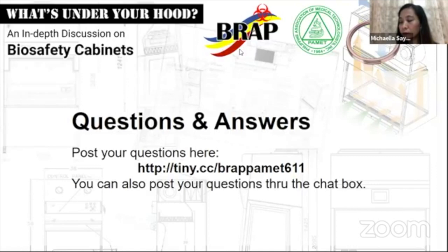Okay. So, last question. What is the indication that you replace the HEPA filter? Oh, the indicator that you replace the HEPA filter. One, if you're in the laboratory and someone is servicing your biosafety cabinet, you should be there to ensure that they don't touch other contaminated materials, and to ensure that they install the right parts. Another check would be your calibration and certification procedure. If you replace your filters because they are clogged, definitely when you get it certified, it should not be clogged anymore. But aside from those two things, I cannot imagine another way to ensure you have new HEPA filters.